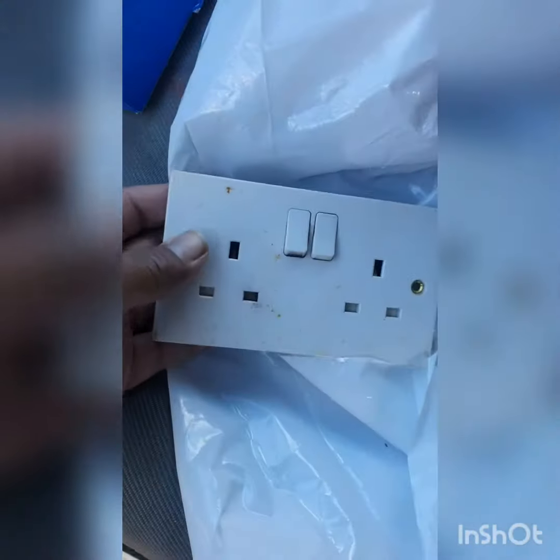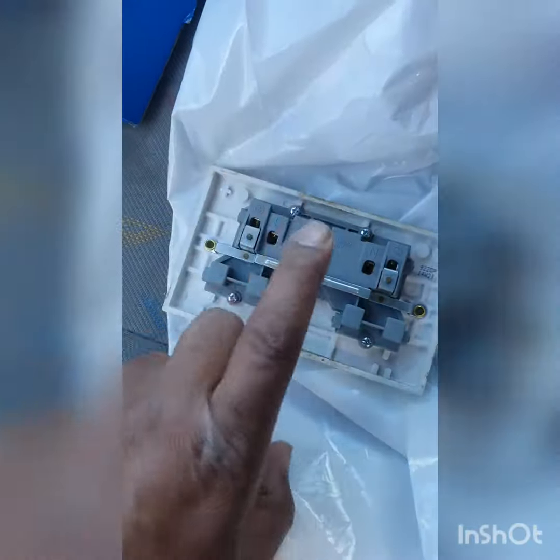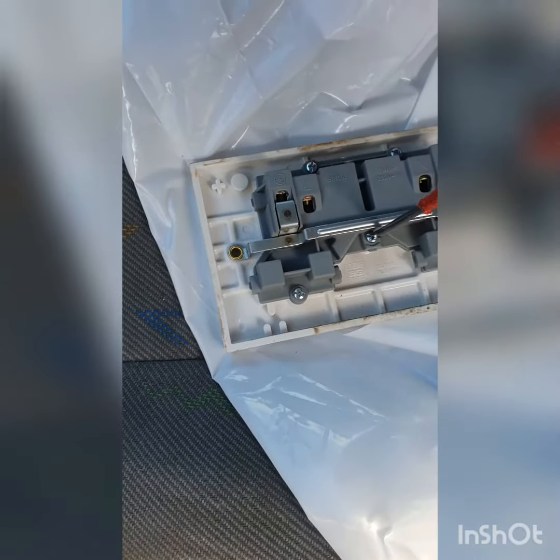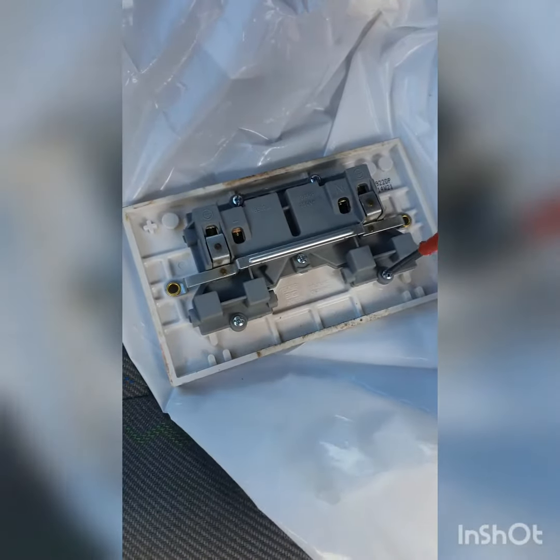Hello guys, I just made this video to help others if they come across this kind of issue. I went to a property where the MCB circuit breaker was tripping. This socket outlet looked dodgy to me because there was char around the buttons. I replaced the socket and the issue was resolved — I was right, there was something wrong with it.